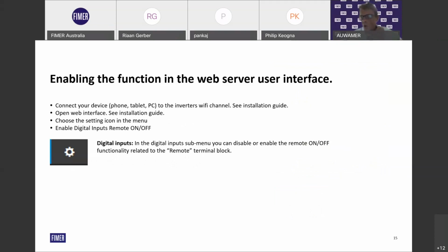As I mentioned before, in all the inverters, when you go through the commissioning stage, you connect to the inverter, connect it to the customer's Wi-Fi, and set the country code, time and date. If you're using an energy meter, you can do it all within the web server. Then to activate the remote function, the DRM0 function, you go into the menu, open the cog wheel settings, go into digital inputs, and enable the remote on and off. It's quite simple.